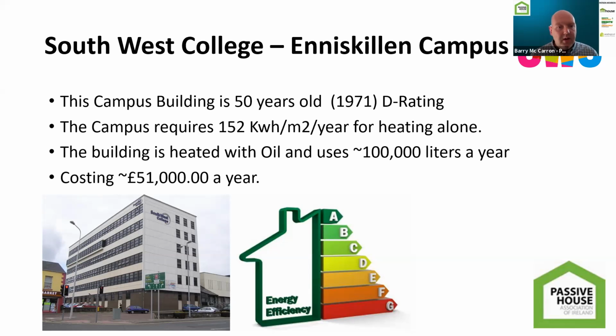I went to the caretaker and asked about oil usage. Depending on the seasonal nature year on year, the building averages about 100,000 litres of oil a year to heat it. Oil prices fluctuate, but on average you're talking about 51 to 52,000 pounds a year to run that building, which is just coming up on 50 years old now, and it's a D-rated building.